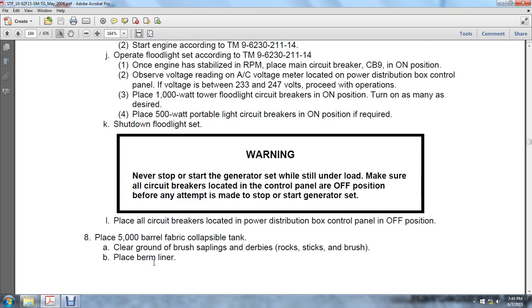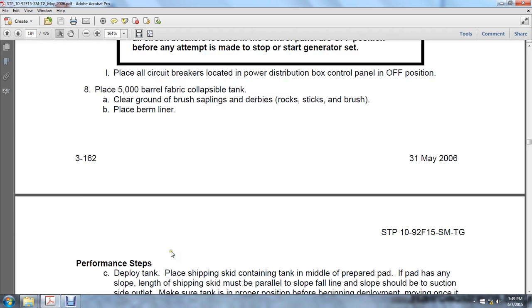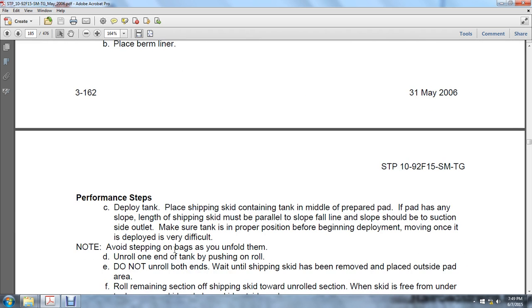Place a 5,000 barrel fabric collapsible tank. Clear the ground of brush, saplings, debris, rocks, sticks, and branches. Place the berm liner. Deploy the tank. Place the shipping skid containing the tank in the middle of the prepared pad. If the pad has any slope, the shipping skid must be parallel to the slope fall line. Slope shall be to the suction line side.